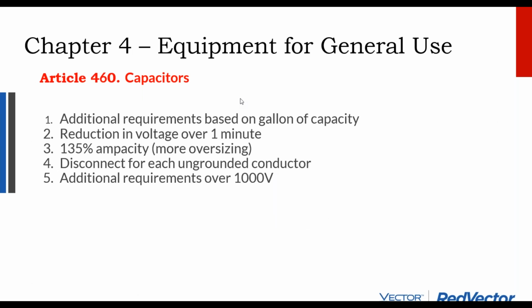Let's see. I guess we were talking about 480, but this is kind of a code review. In this adjacent section to 480 with batteries, we have 460 for capacitors. I think what's really interesting about capacitors is that in most national electric code, in your battery circuits, when you're sizing your cable, you're looking at the ampacity of the battery circuit, and then you're adding 25% additional headroom for that.